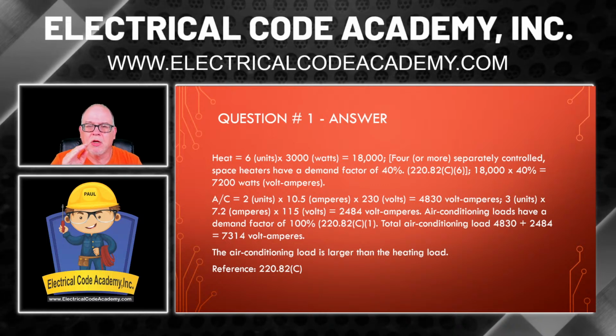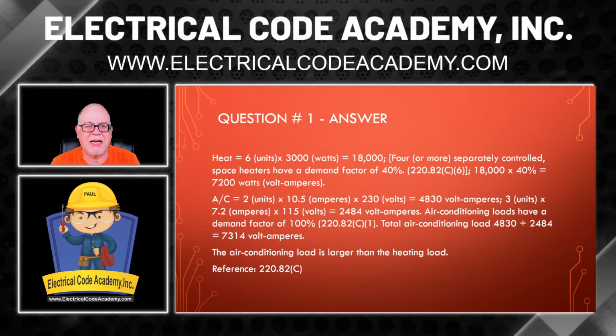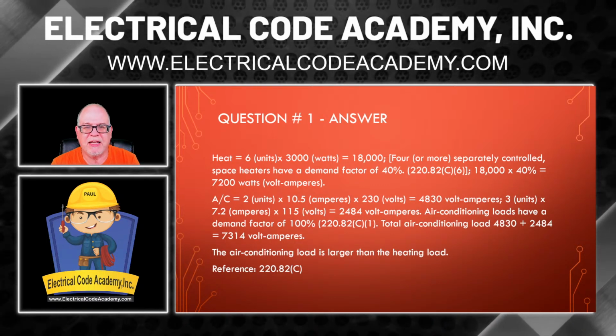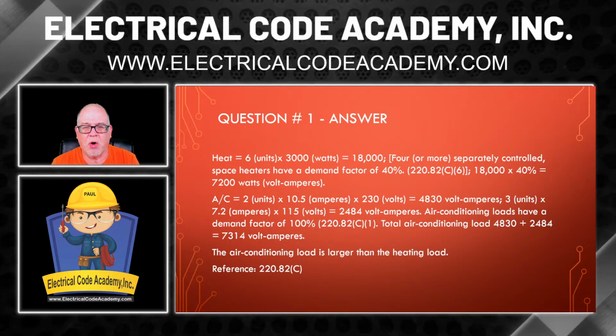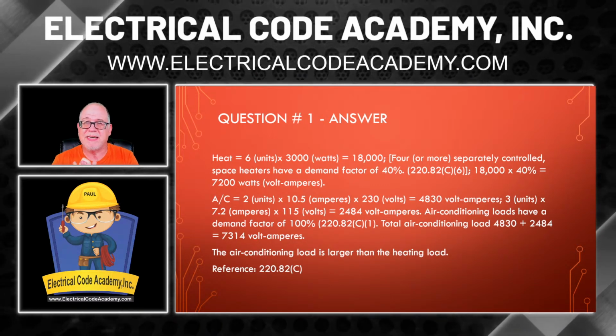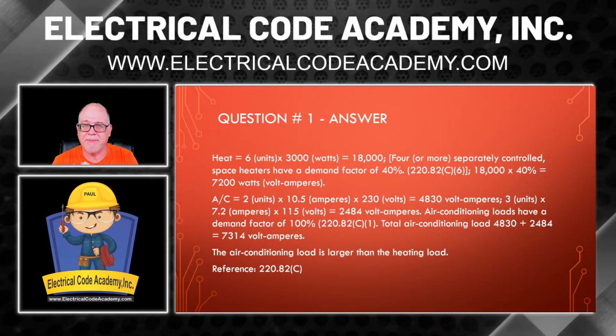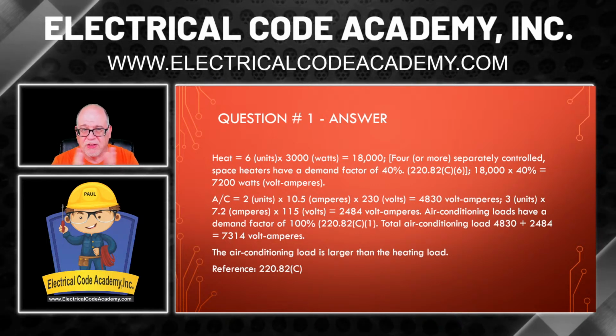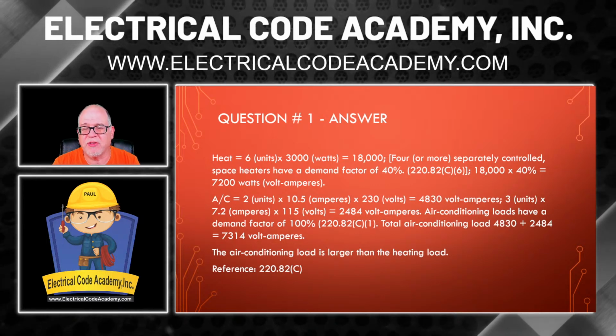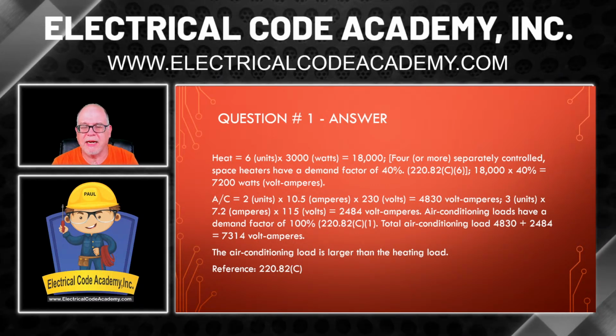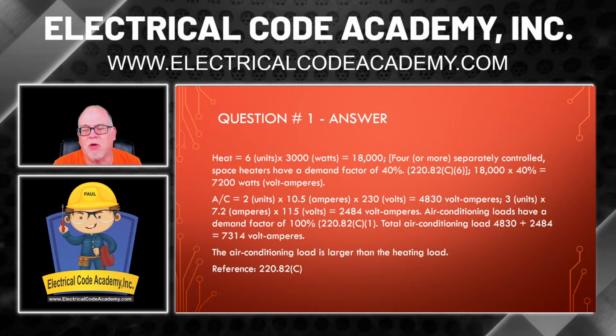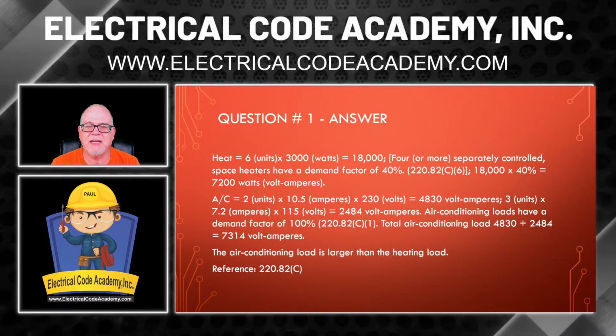All right. So now we want to do 3 times 7.2 times 115. That's 2,484. So all we're going to do is remember, we take them at 100%, right? So we're going to add the 2 together. 4,830 plus the 2,484, add them together. That's 7,314 VA.